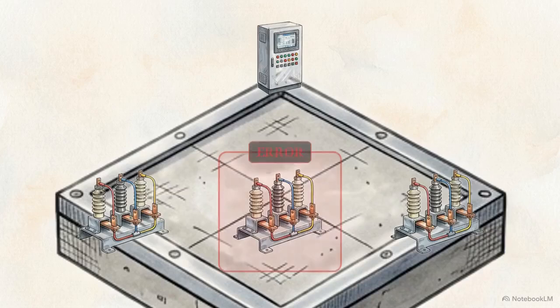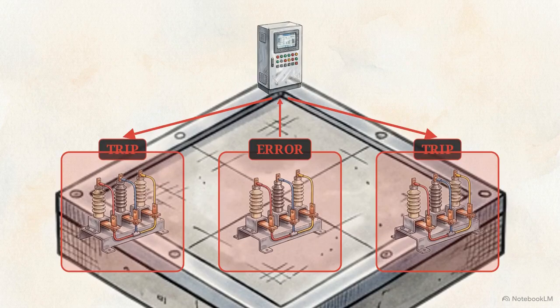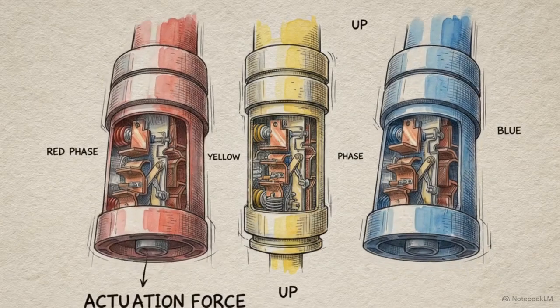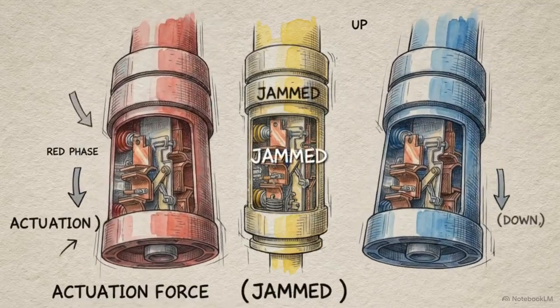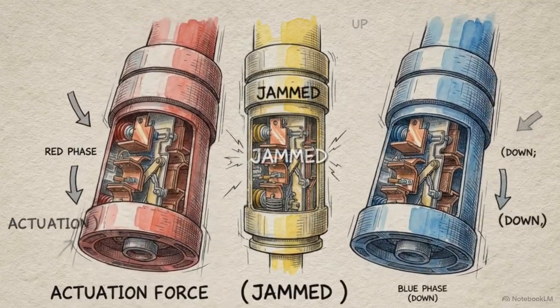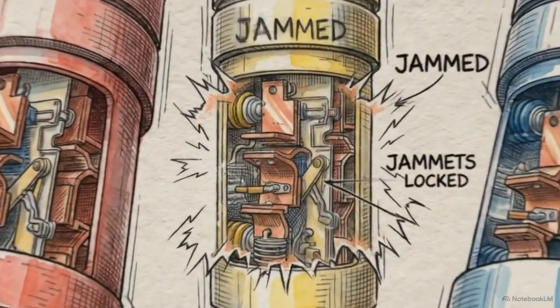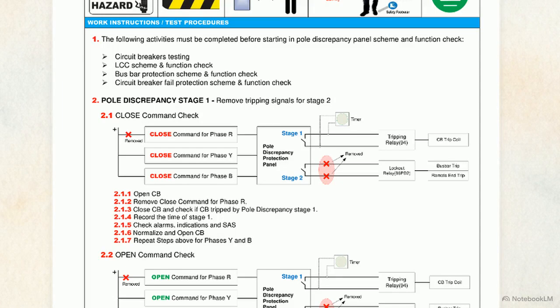Beyond hardware, we validate system-wide protection logic. The pole-discrepancy scheme protects the entire power grid if a single massive breaker phase fails to operate in sync with the others. This schematic for the Stage 1 test logic shows the removal of the close command for a single phase. The scheme must detect this discrepancy and trip the local breaker within the approved time delay.